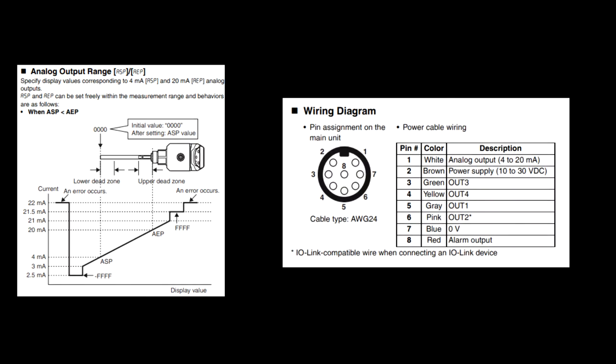Now that the FL is successfully calibrated to the liquid it's trying to detect, we can move on to the output methods that will tell your system the specific level that your tank is at. The most common method would be to use an analog 4 to 20 milliamp output. To set this up, make sure you are using the white wire as your analog wire.